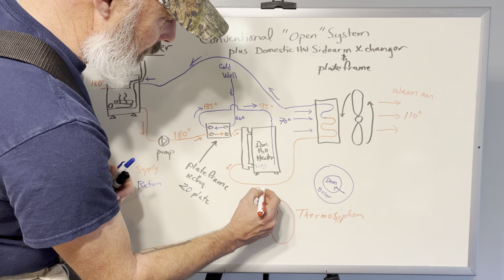It's not a big temperature drop, because remember that sidearm heat exchanger is a relatively low capacity. It does its work over time. So it goes in 180, comes out 175, goes to your coil. If your furnace or air handling unit, whatever, turns the fan on because you need heat, it gives you heat. That water will get cold in that heat exchanger, going back to the boiler to get reheated. So that's the boiler side of things, with no domestic water being used.